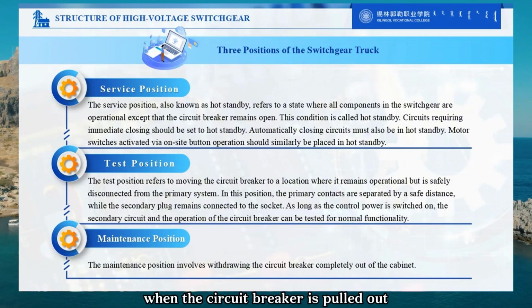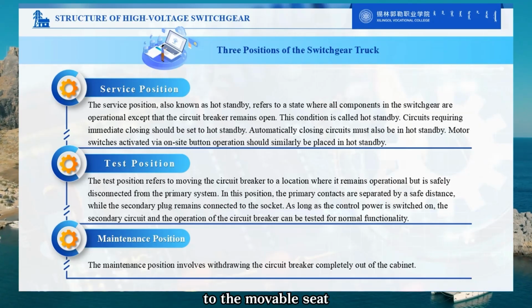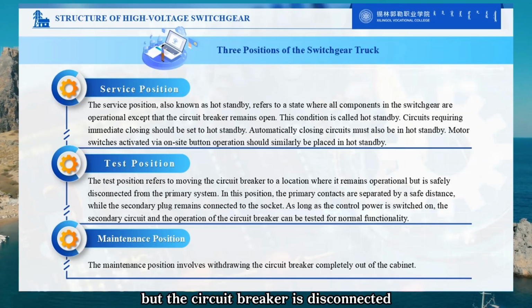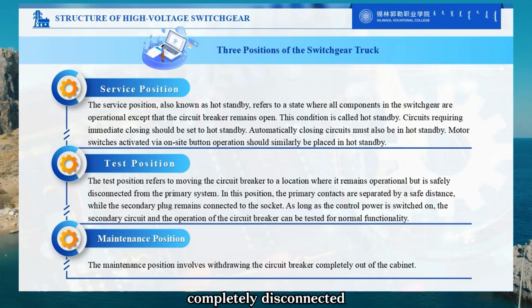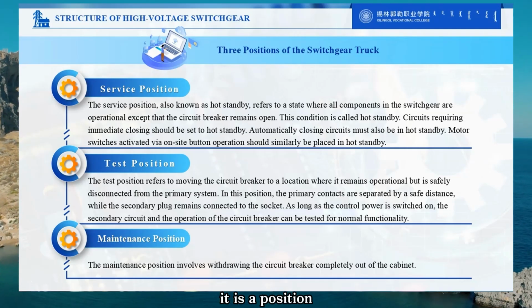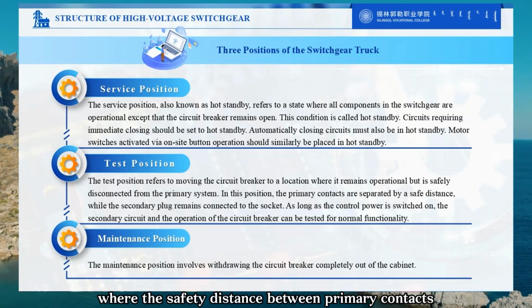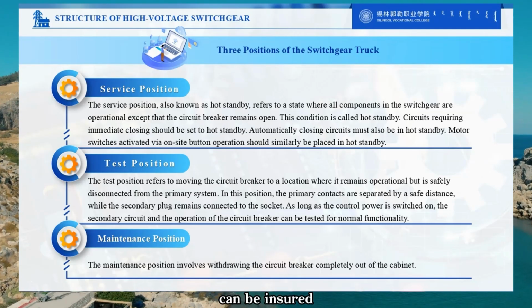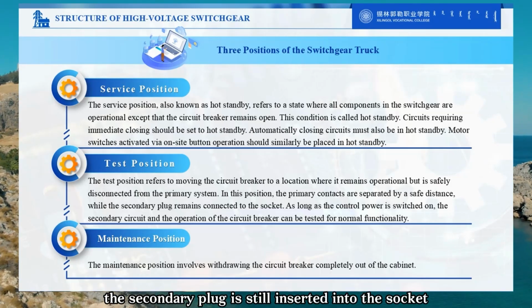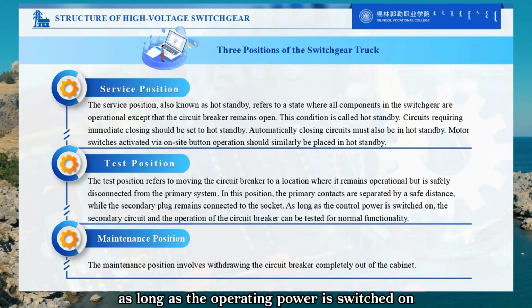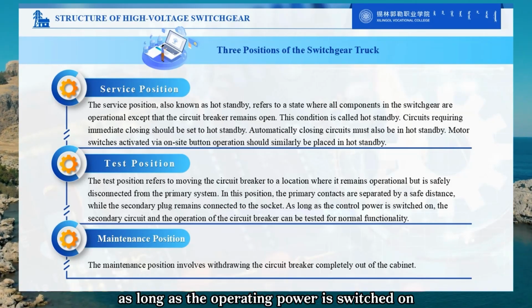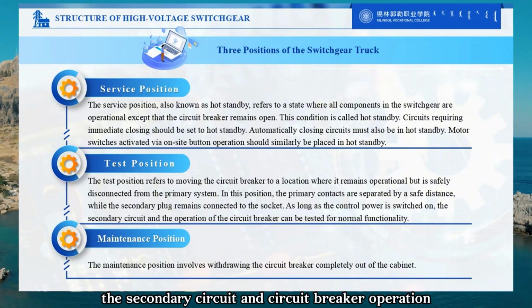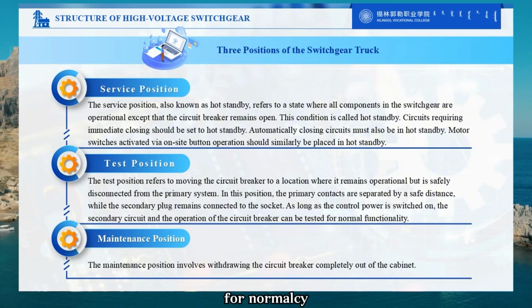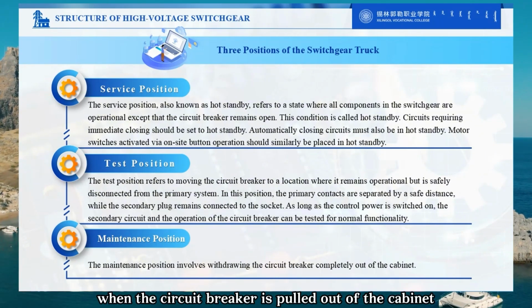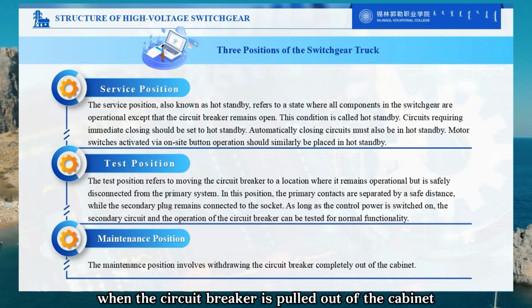The test position is when the circuit breaker is pulled out to the movable seat, but the circuit breaker is disconnected from the primary system, completely disconnected. It is a position where the safety distance between primary contacts can be ensured. The secondary plug is still inserted into the socket. As long as the operating power is switched on, the secondary circuit and circuit breaker operation can be tested for normalcy. The maintenance position is when the circuit breaker is pulled out of the cabinet.